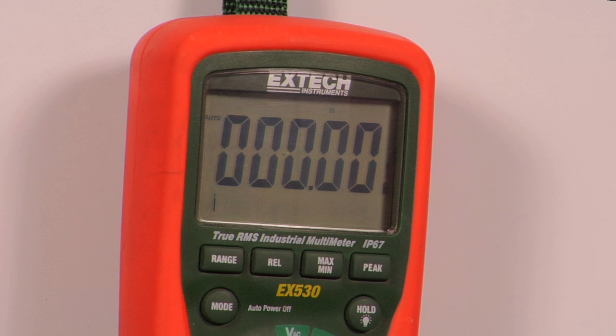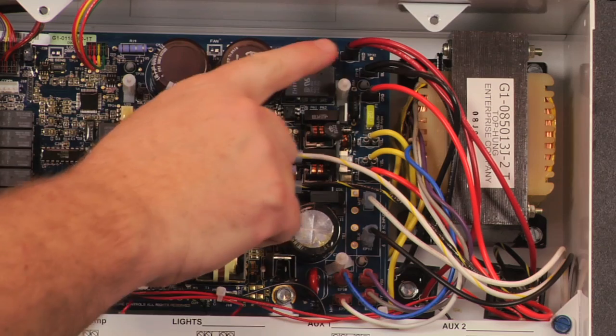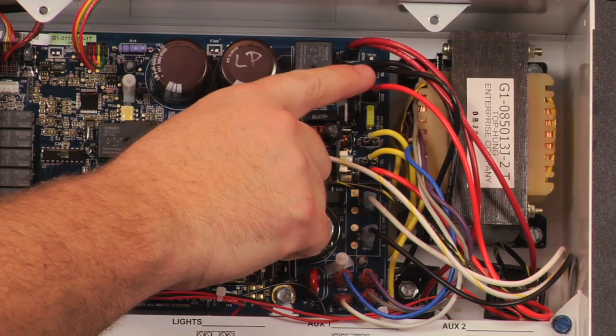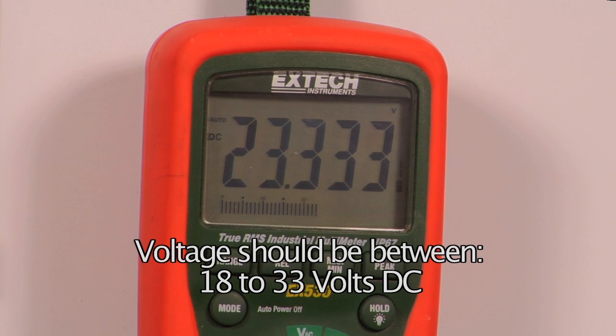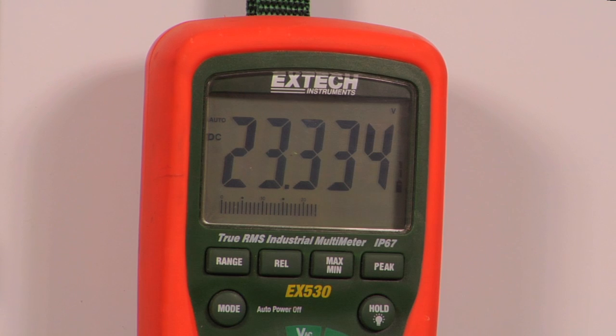If the voltage between the orange terminals is good, measure the voltage between the red and black terminals on the main board. The voltage should be 18 to 33 volts DC. If the voltage is low or not present, one or both of the rectifiers are bad and should be replaced. If the voltage between the red and black wires is good, the main board is bad and should be replaced.